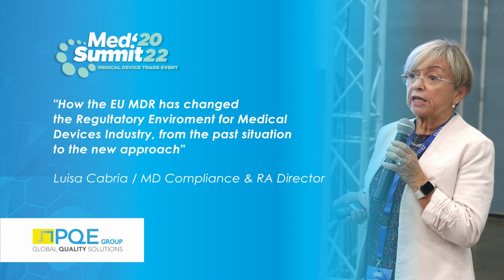This is important also for the legacy devices. I mean devices that were already CE marked in accordance with the old directive, and now you want to migrate, you want to renew the certificate in accordance with this regulation. So you need to reassess the compliance of the device. The demonstration of compliance of the device is in the technical documentation. I told you in the article, talking about the article 10, one of the obligations of the manufacturer is to have a technical documentation. The technical documentation shall be in accordance with the Annex 2 and Annex 3 of the regulation. These two annexes are very detailed and provide you instruction, guidance, how to prepare the technical documentation.